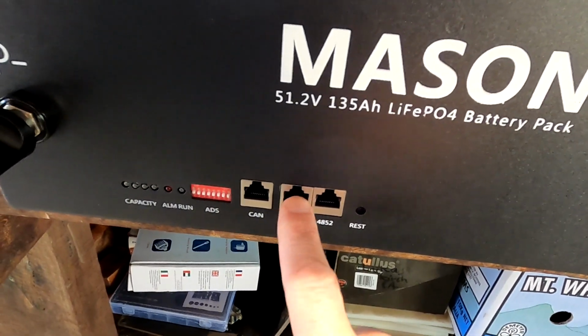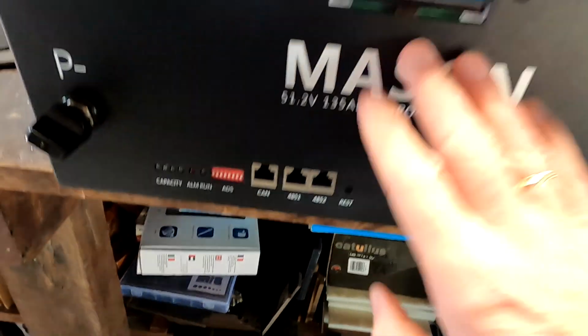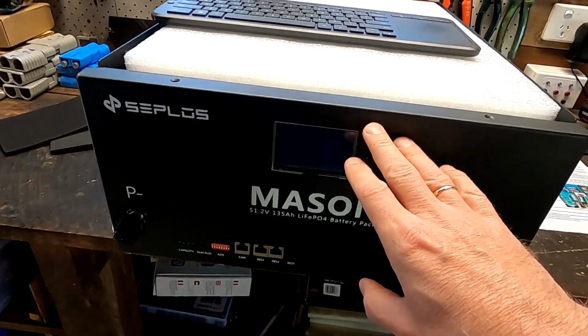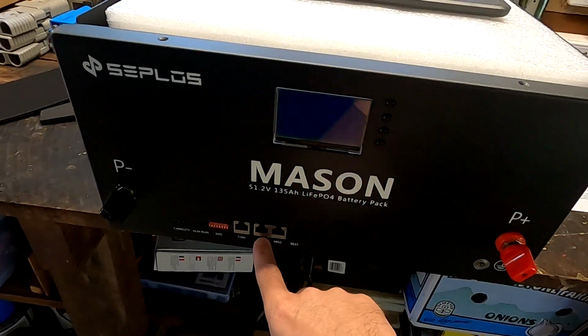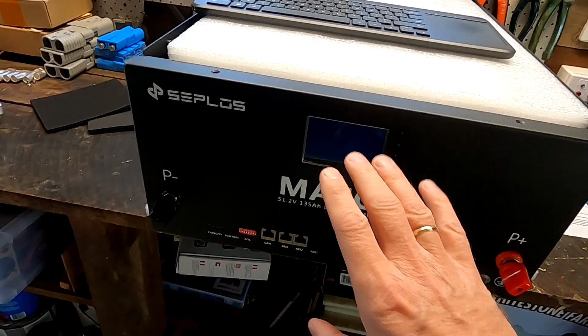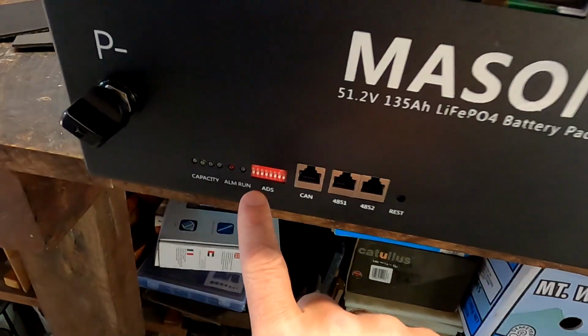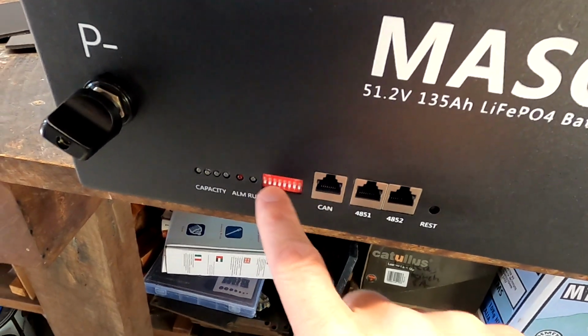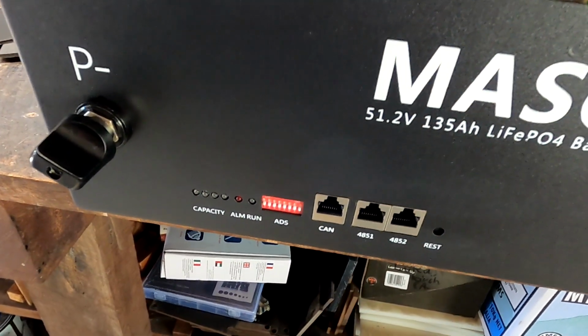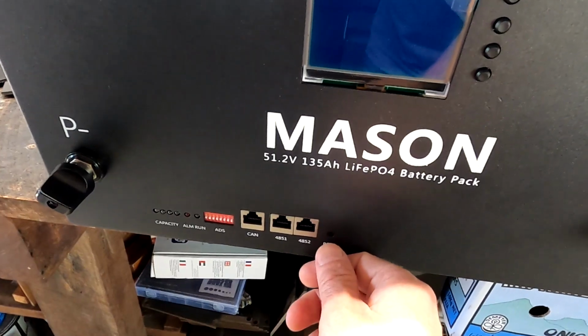I think you have 2 ports to daisy chain these devices together. If you have more than one, or if you want to expand over time, you just connect them to each other and they will all listen to the master. You can set the master-slave function with these dip switches on the BMS directly, and you only have to turn on one device, then all the other devices will turn on. They all listen to the master - that's how it should be, right?